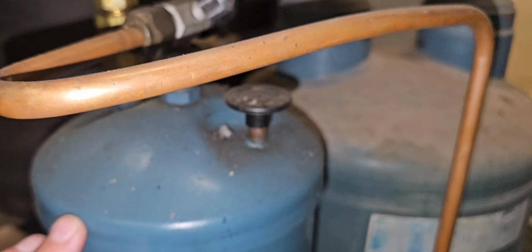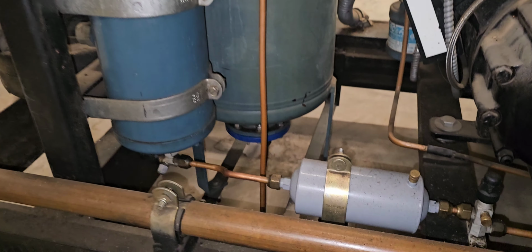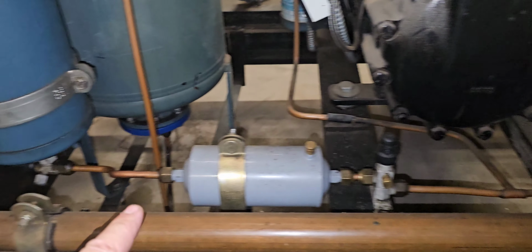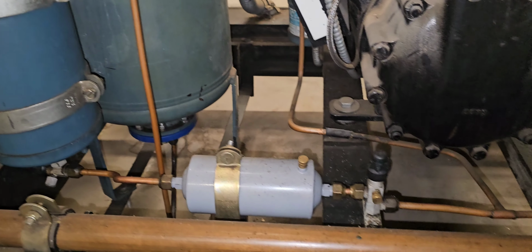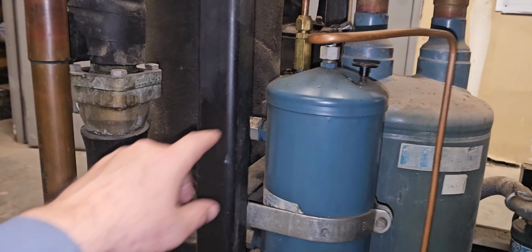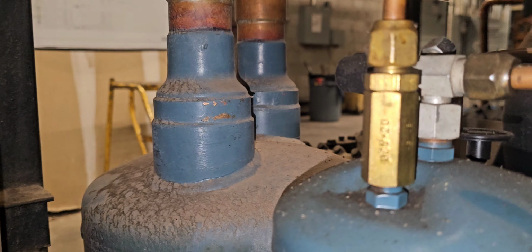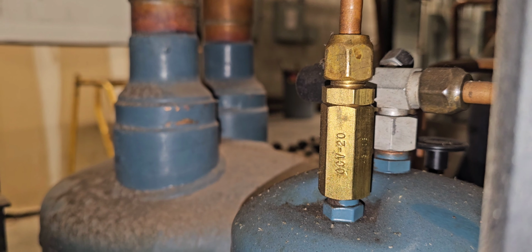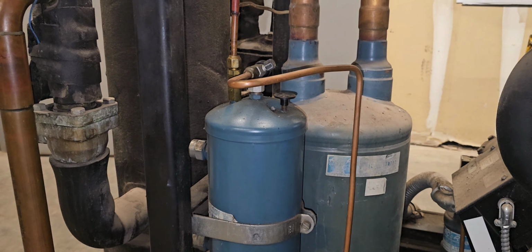Now, what's the biggest difference with these? You have a low pressure reservoir, which means you don't have any oil differential valve on this line. Remember, with that high pressure system, you were coming off of that separator, you hit a Y valve, an oil differential valve, and then you went into your compressors. Whereas here, we have this OCV, this oil check valve. This one right here, let's see if we can see it. That's an OCV 20. So what that means is it's gonna keep this reservoir 20 pounds above suction.